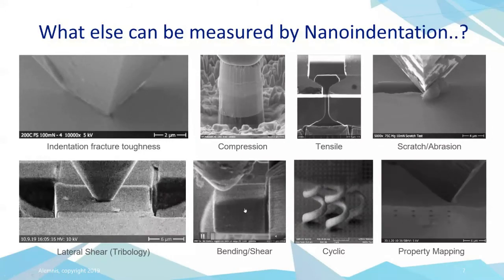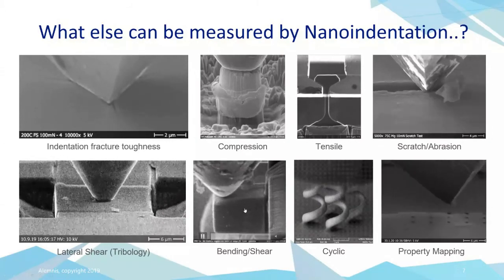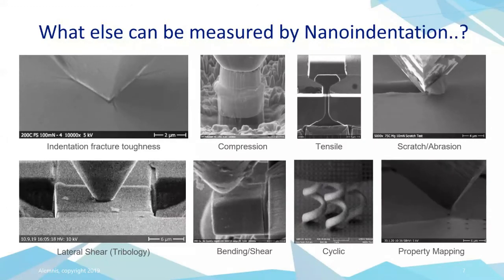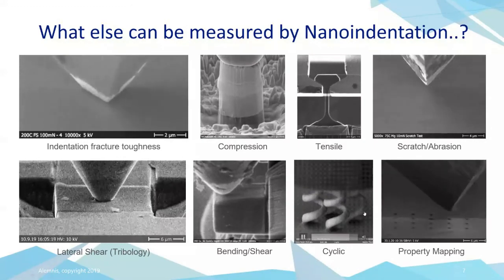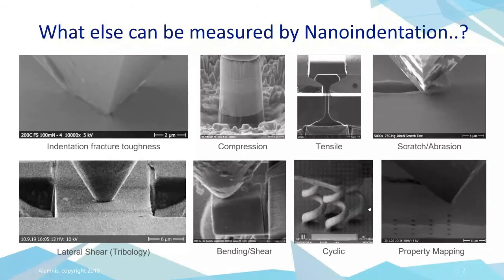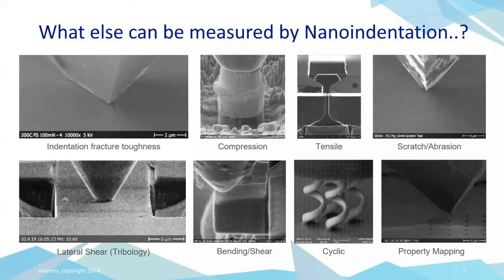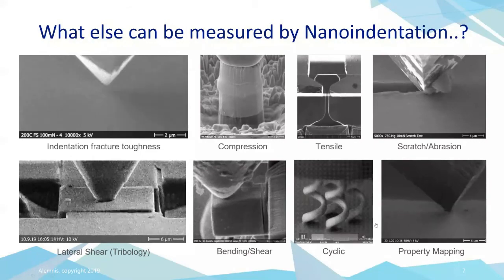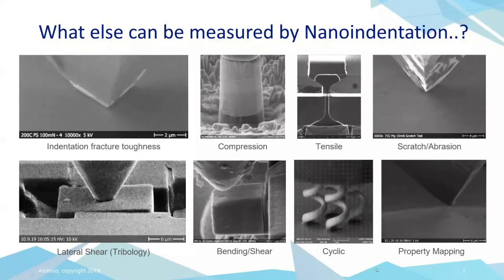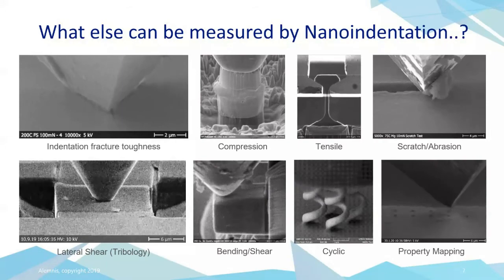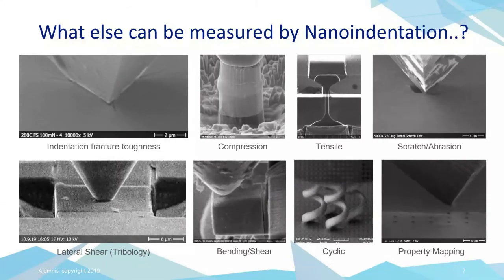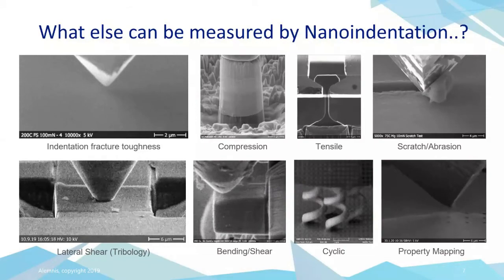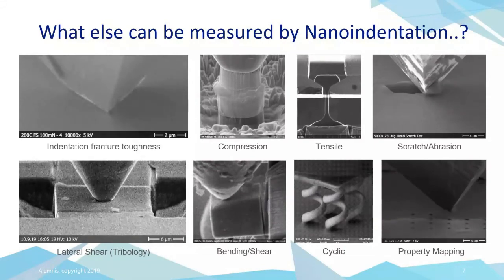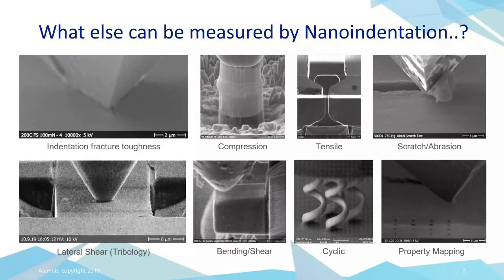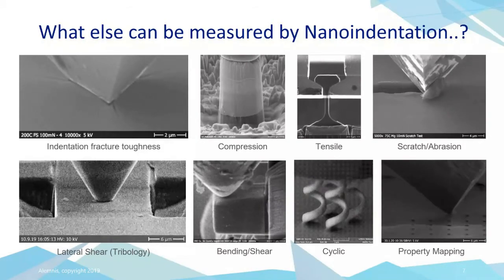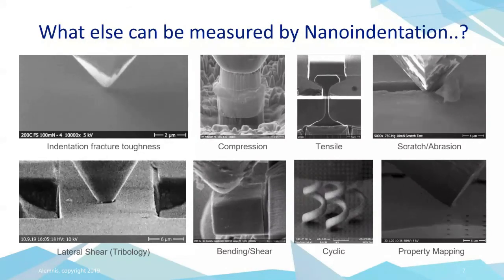Then we've got bending and shear, so beam bending experiments using beams that are cut by focused ion beam. Cyclic indentation testing. So here we're looking at a 3D printed structure, very small, and we're actually doing a cyclic indentation test. The advantage of instrumented nanoindentation is you can program the indenter to do whatever you want. It can do a single cycle, a multi-cycle, a sinus mode cycle, a dynamic test, a pause, a creep test, a stress relaxation experiment. Highly programmable to do basically whatever you want it to.